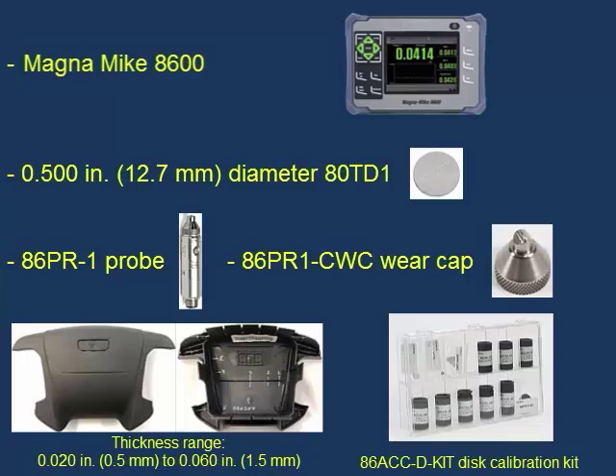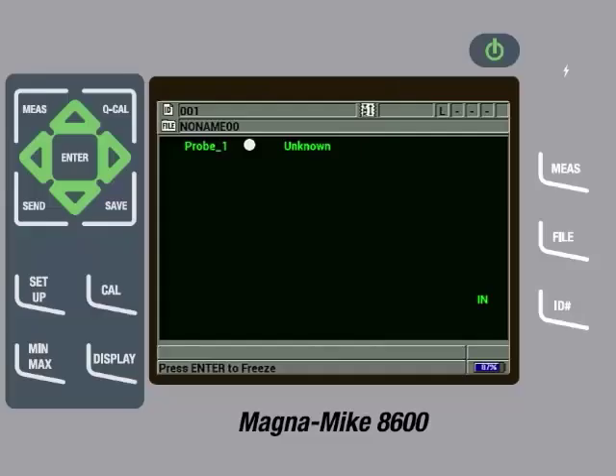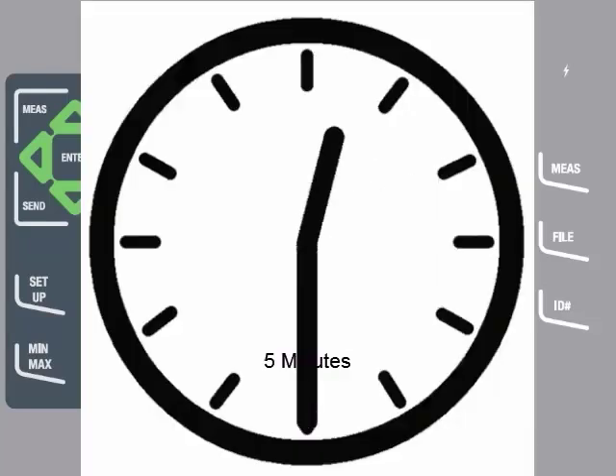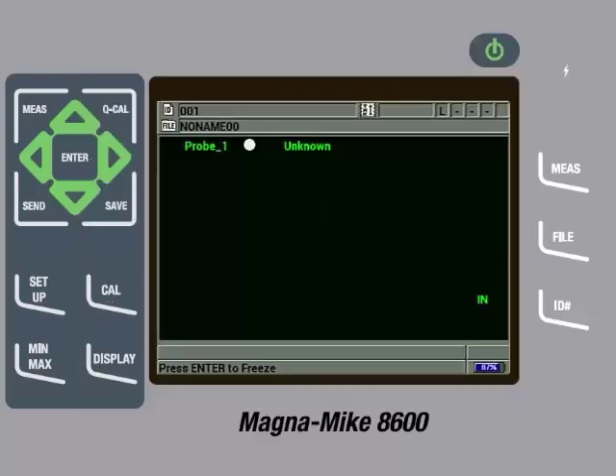The first step would be to connect the probe and probe cable to the instrument and then turn the instrument on. It is important to let the instrument warm up for at least 5 minutes before using it, so the probe can reach a steady state temperature condition. The Magna-Mike 8600 can auto-detect the different size target balls, but it cannot auto-detect the disc or wire targets. Therefore, we will need to tell the instrument what target we are going to use.